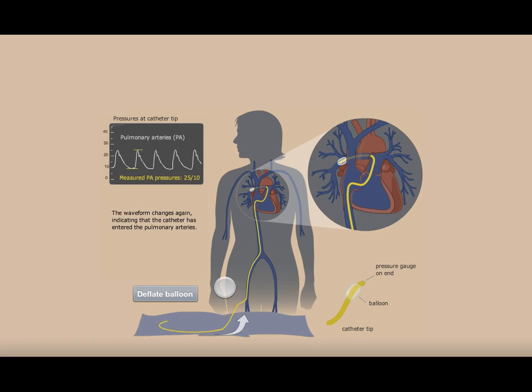Here are some key points to consider as you use the diagram. The catheter has a small balloon near its tip and a pressure transducer, a kind of measuring device, just beyond the balloon. The balloon can be inflated via a small air-filled syringe, not shown here, attached to the other end of the catheter. The waveform for the measured pressure is shown on the screen toward the left side.